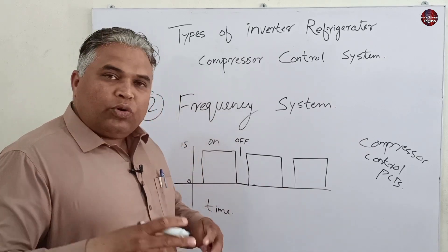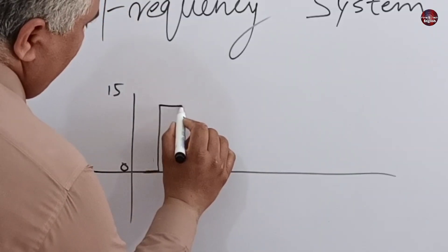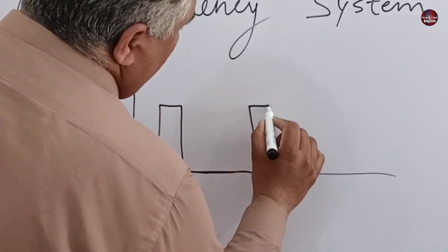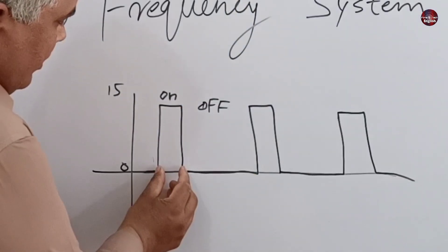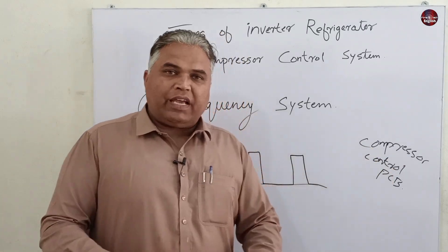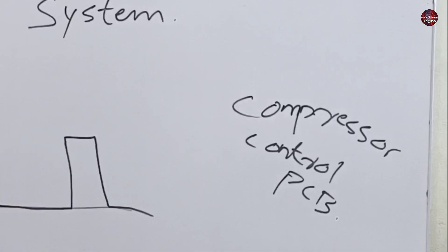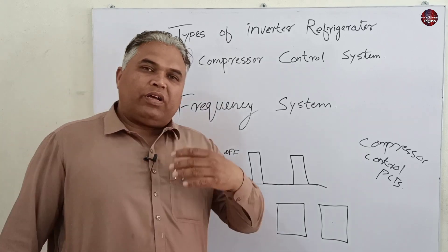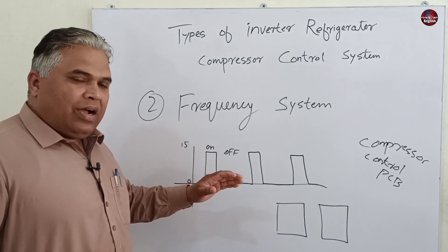When the cooling in the refrigerator is completed, the signals will change — the voltages turn on but turn off quicker, the off time of the signals increases and the turn-on time is reduced. The compressor control PCB will understand that the refrigerator doesn't need much cooling. In this system, two control boards are used: the main PCB and the compressor control PCB. This control board communicates through the on and off time of the signals. Because it is a very simple and easy-to-understand control system, it is available cheaply in the market.